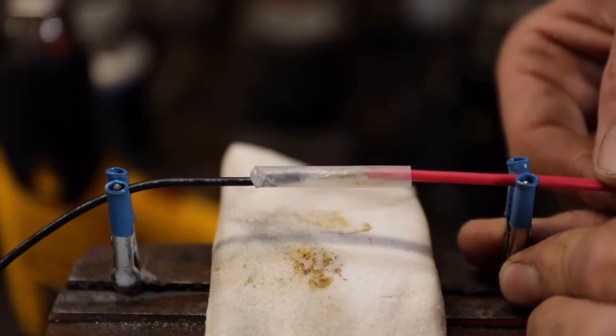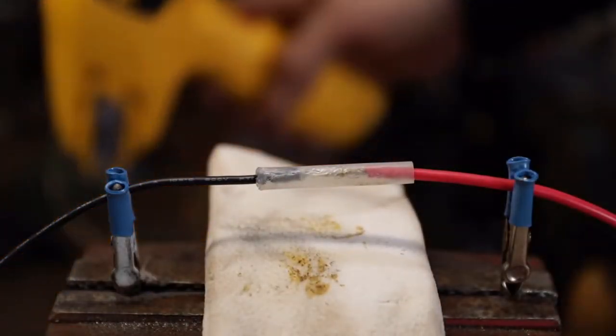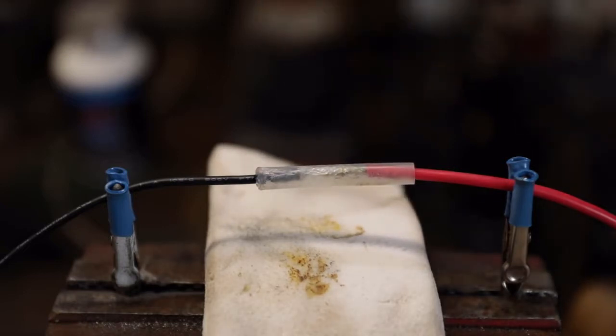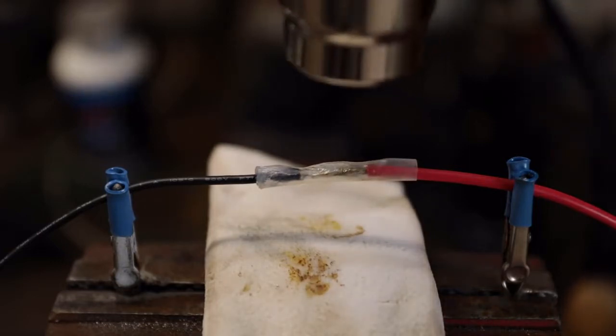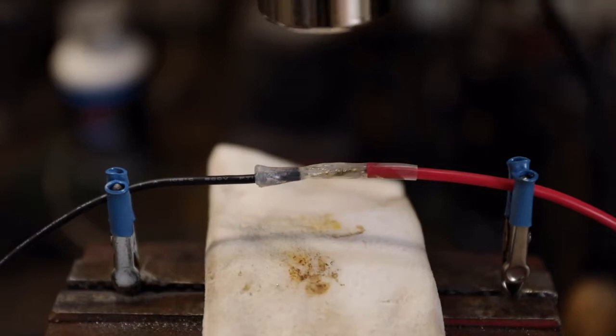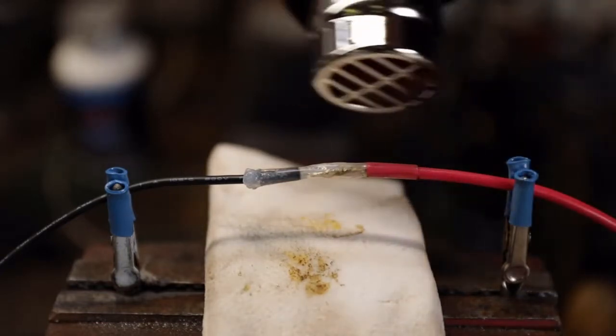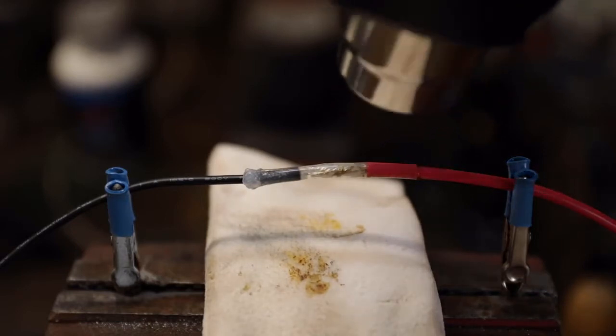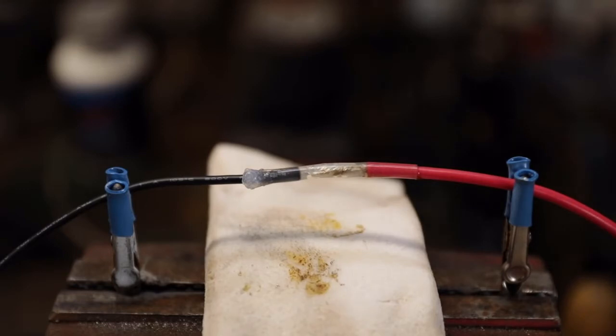Your shrink tape will shrink on the ends about 10 percent, so I'm pretty liberal with that and give myself plenty of tubing. You can use a heat gun, lighter, or torch, but the lighter and torch will tend to burn the wire if you're not careful. Start from the very middle and you'll see it starting to shrink, then work to the outside edges. You'll see that silicone making that seal as the shrink tape tightens around the connection. That looks pretty good right there.